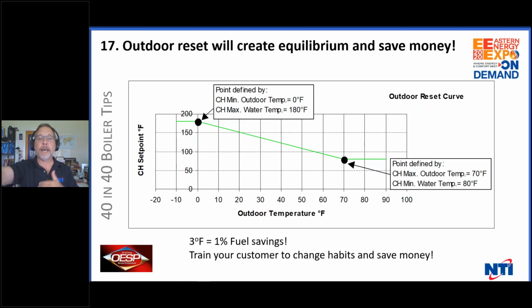The colder it is outside, the faster the transfer of heat. The warmer outside, the less the transfer of heat. Outdoor reset will save you 14%. I've done this with Tekmar controls since the 80s when I first saw them with cast iron boilers. I do it today using modulating condensing, high efficient boilers that come with outdoor reset.